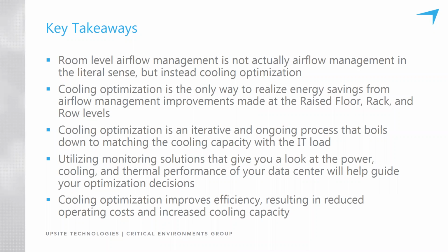So I'm going to go through some of the key takeaways, and I think, Isaac, this will be made available after the presentation's over. We talked about the top three, not necessarily airflow management, but cooling optimization, especially when we get to the room level. And like Lars said over and over again, it's the only way to realize energy savings. All that stuff you've done, all those blanking panels, floor grommets, barrier panels, aisle end doors, all of that up until now has been an expense. But it's your ticket to the dance, and now it's your turn to help realize it.